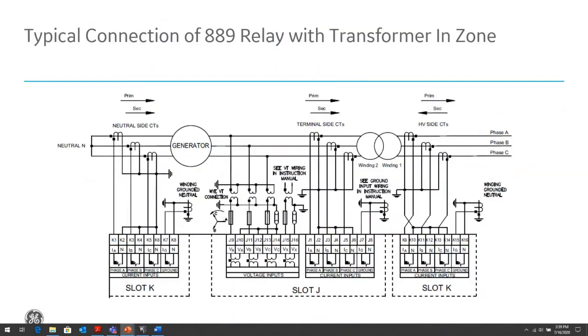This is the 889 connected if you have an in-zone transformer. And you can see, because if you have an in-zone transformer, now you're connected to maybe the CTs in the transformer bushing, so you have to be careful with that connection. Make sure it's properly connected if you're using differential protection, so that for internal faults it adds, and for external faults it subtracts.